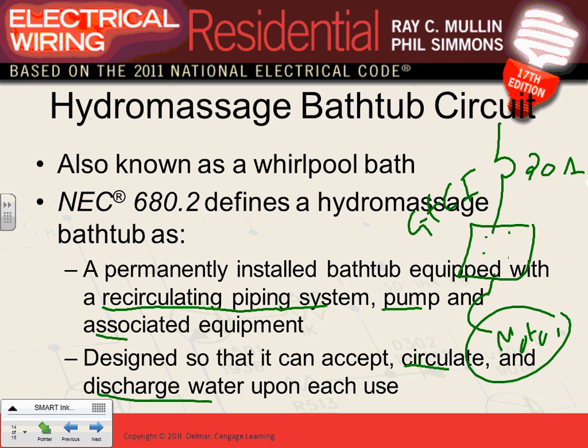Can I have thumbs up, Chad? Cool. Now this motor that works with it, you have to have a cord. That's where your disconnect comes to be, plugged into a cord. You have to have a GFCI receptacle by code because it's water, and you have to have a 20 amp dedicated circuit feeding it. Done.